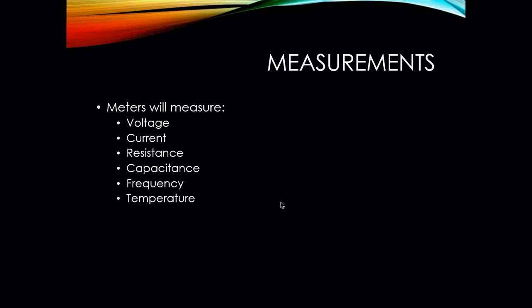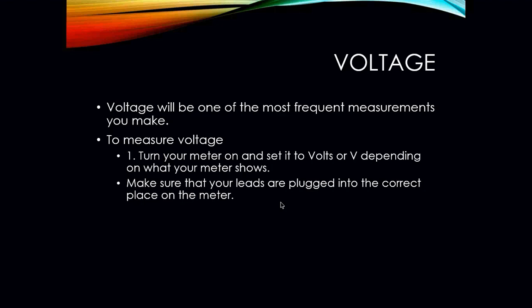Many meters out there have these functions: voltage, current, resistance, capacitance, frequency, and temperature. But it all depends on how extravagant you want to be and how much money you want to pay. Your very basic meter will have certain functions. Voltage is one of the most frequent measurements you take. In order to take your voltage, the first thing we have to do is make sure that the meter is in the on position, and we set it to V, or volts, depending on what your meter shows. You're going to make sure that your leads are plugged into the correct place on the meter. Sometimes if you have them in the wrong leads, it's not going to take the proper reading, or you might just get a scrambled number.